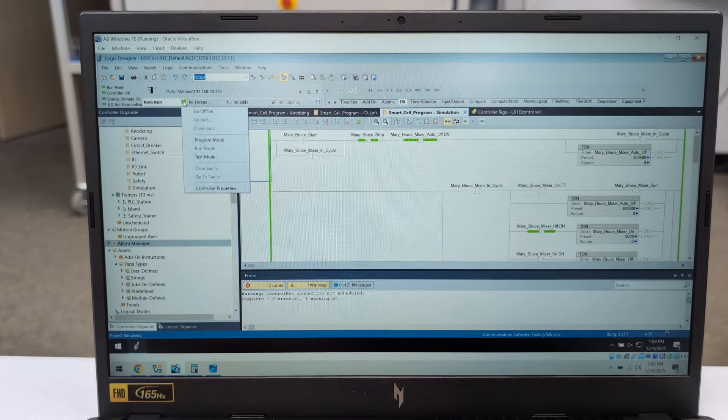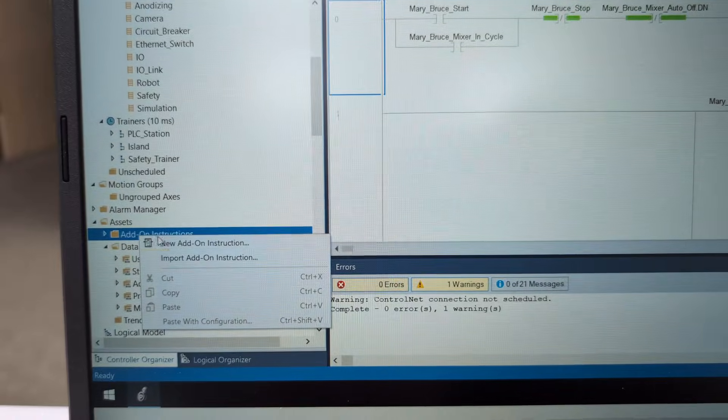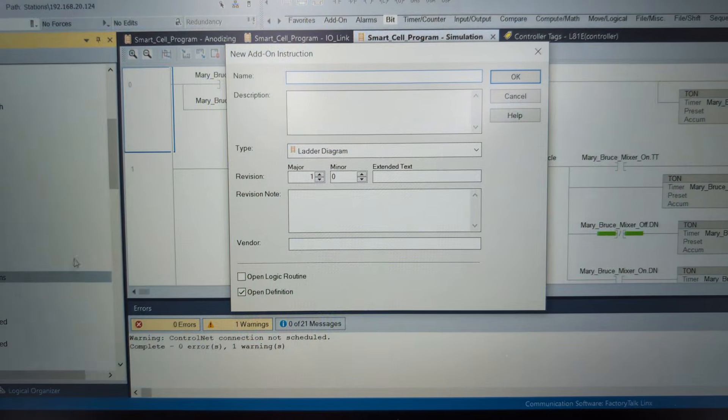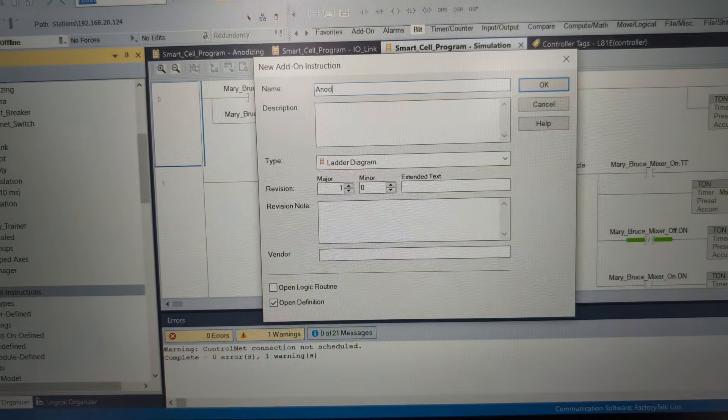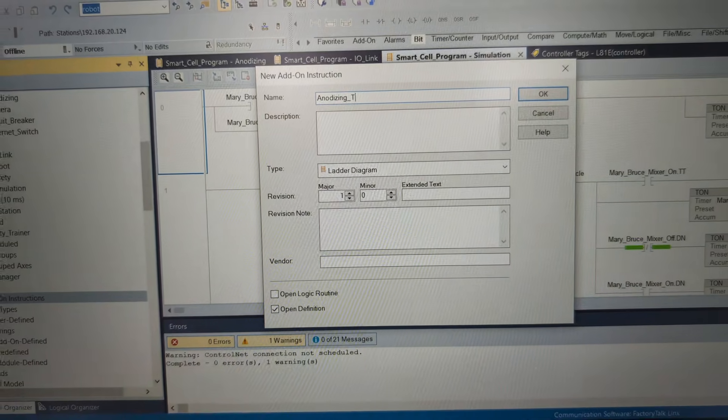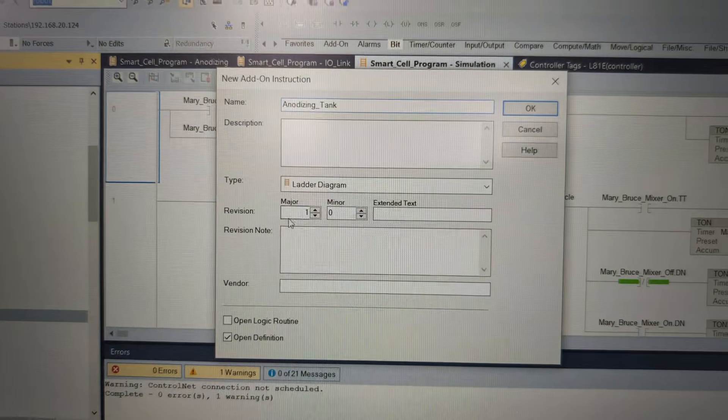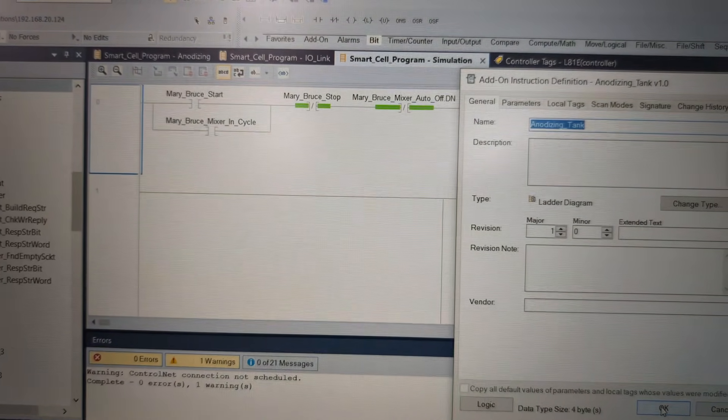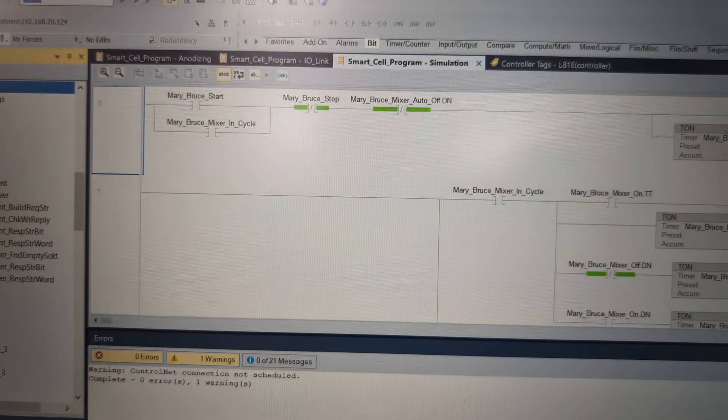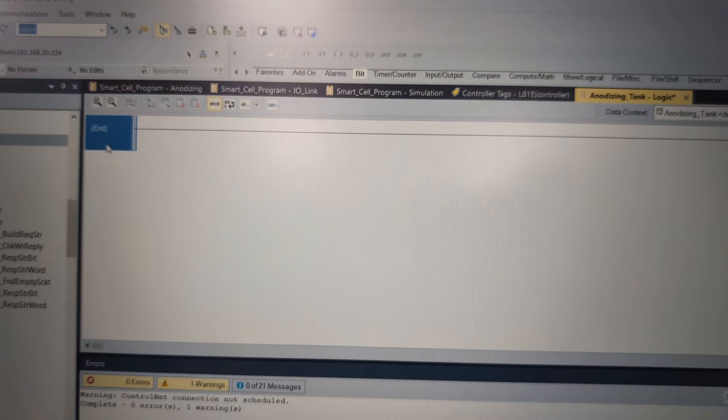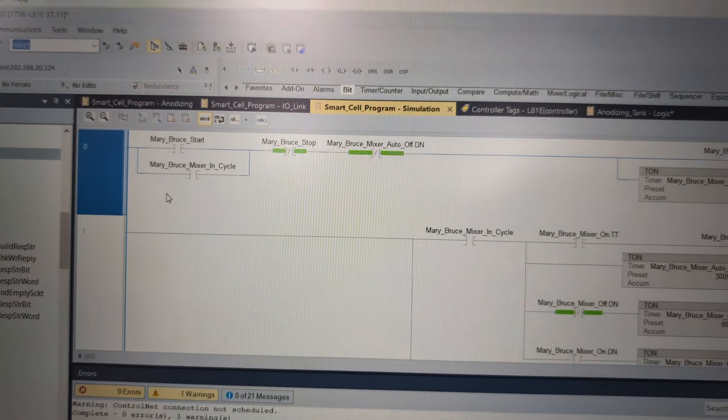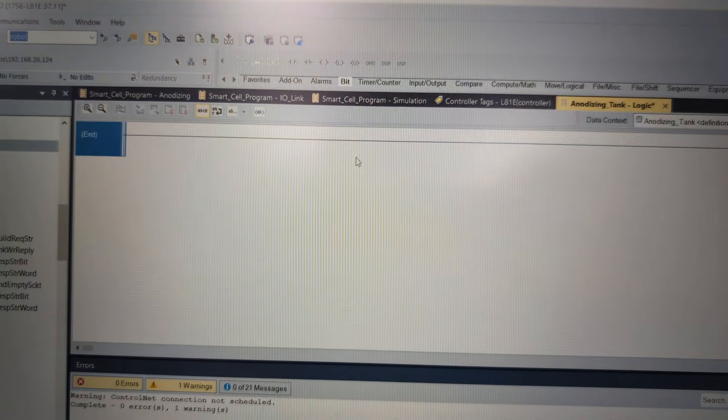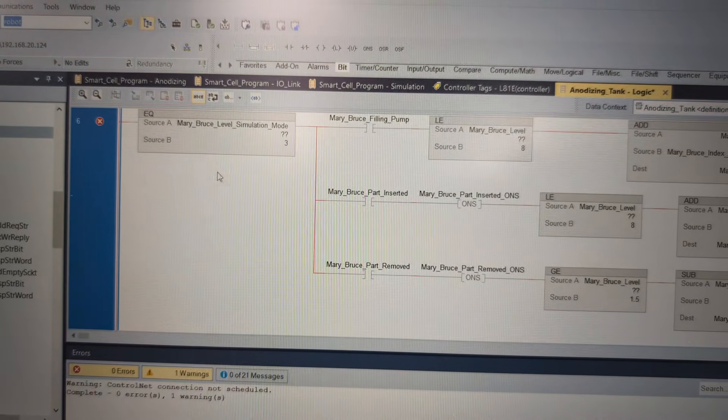In my case I can go offline. I also could just open a second copy of Studio 5000, but I'm going to go ahead and just save this. Then I'm gonna go offline and now we can right click Add-On Instruction, New Add-On Instruction. We're going to call this AnodizingTank - look how good my spelling has gotten at anodizing, folks. We're going to do a ladder for this and hit OK. I'm going to double click on its logic because I typically would create my tags, but I have all my tags roughed out over here. I'll do a Control-A, Control-C, then go over to AnodizingTank and paste all that in. We're going to get lots of angry stuff in here.